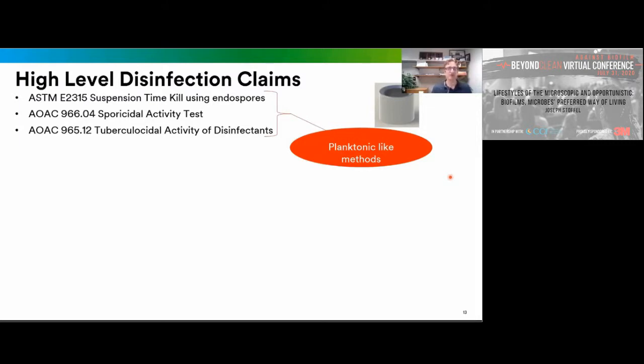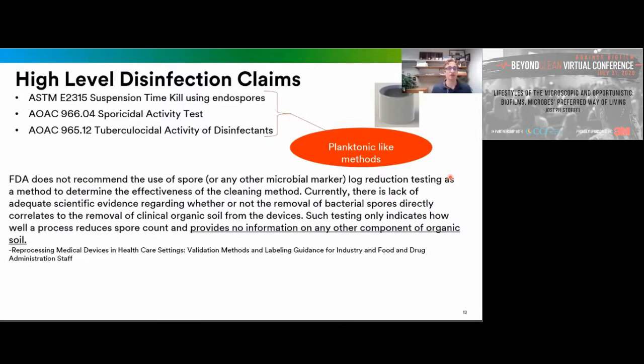It's interesting—in a reversal from what we've seen on the combination device side, the FDA agrees that just demonstrating log reduction values of endospores is not necessarily the best way to show you're cleaning a device. It's insufficient, because spore count reductions don't necessarily correlate to organic load reduction.